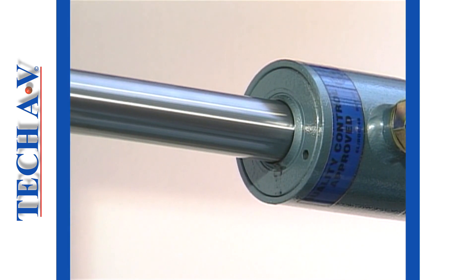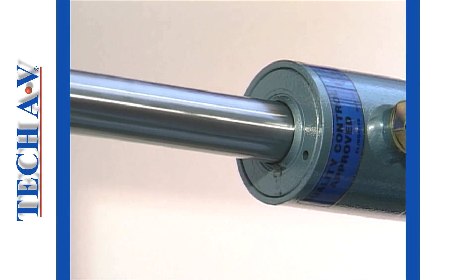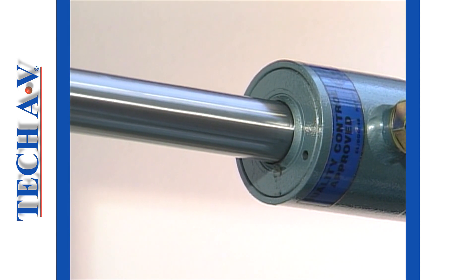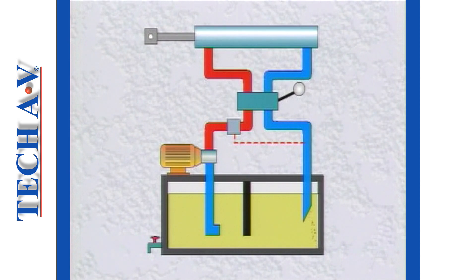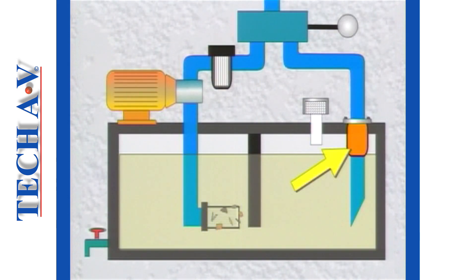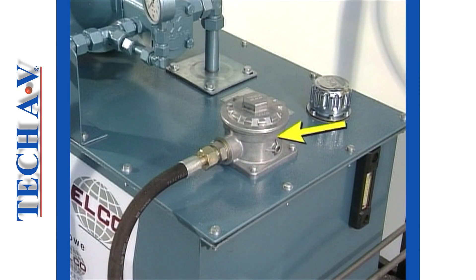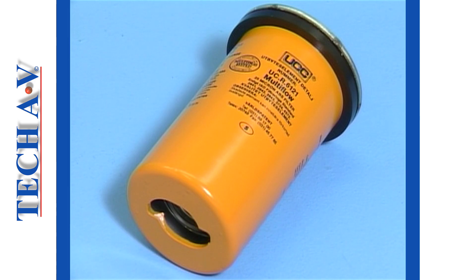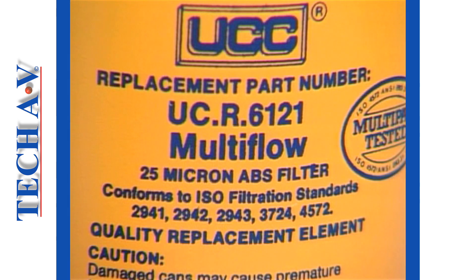Dirt will often enter a system from the outside, through, for example, worn cylinder seals. If unchecked, this dirt will find its way into the return line and, as previously mentioned, result in a build-up of sludge at the bottom of the tank. A well-designed system will include a return-line filter, usually mounted directly into the tank, as seen here. The common rating for return-line filters is 25 to 30 microns.